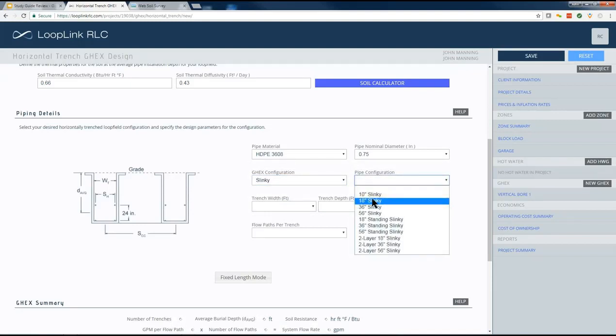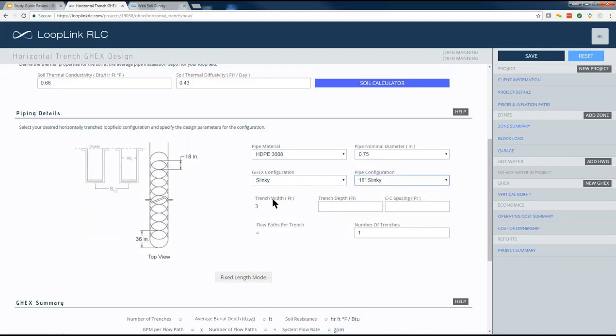These are all the options that we have inside the program. So there's an 18-inch pitch slinky, one that you'll commonly see used. Notice that the diameter of each coil is 36 inches. So when this pipe is extruded in the manufacturing facility, it's pulled off the extrusion machine when it's somewhat warm, and they coil it. And those coils are about 3 feet in diameter, about 36 inches, and the pipe cools that way. So you notice it's got a little bit of natural memory to it. So you generally don't want to fight the memory of the pipe. Just stay with the 3-foot diameter coils. And then by 18-inch slinky, what we mean in terms of the pitch is the spacing from one point of a slinky coil to the same point of the next.